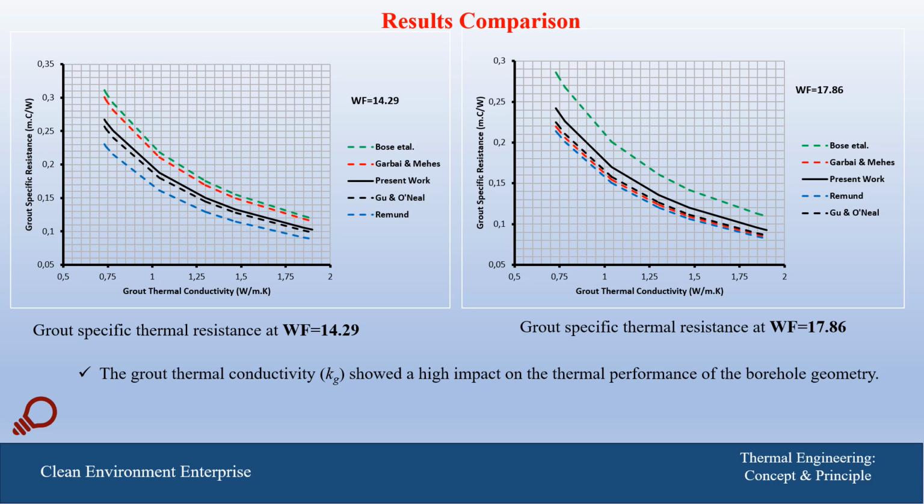So again, the same trend of the variation of the resistance, and we can conclude that K_g, which represents the grout thermal conductivity, has a high impact on the performance of the borehole.